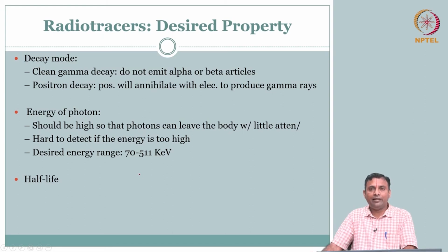Clearly that means some detector material is going to be engineered for this purpose. Because in X-ray we didn't really deal with so much energy. We beam hardened it, and we didn't really worry about that. Whereas here, too high is also a problem, and therefore a desired range is this one.